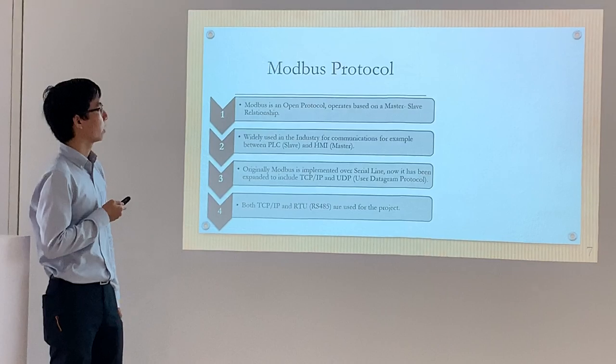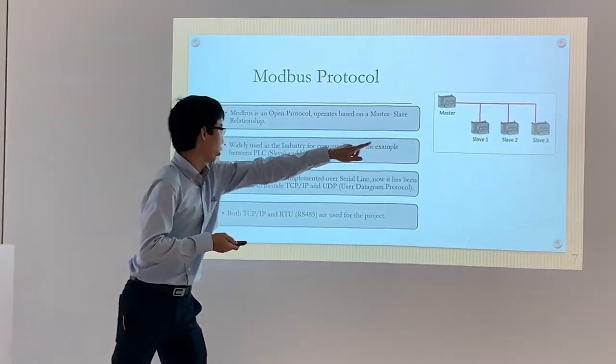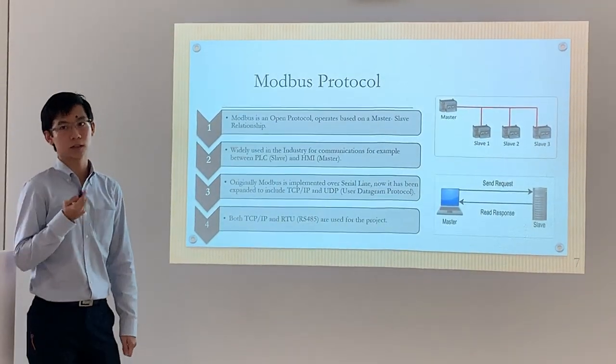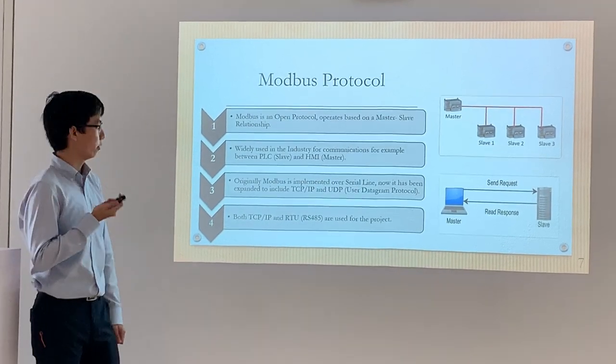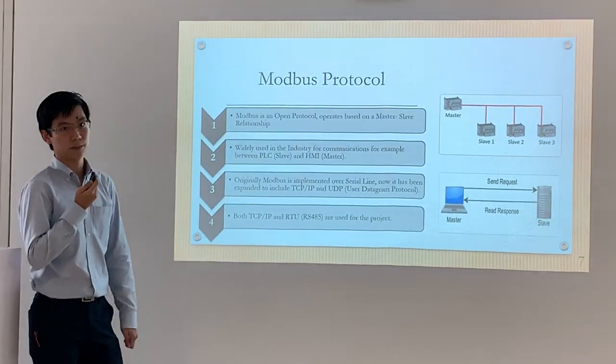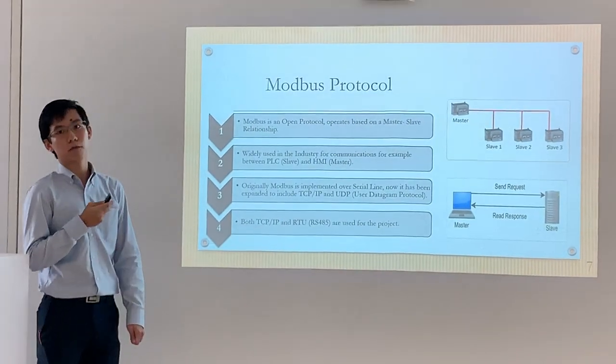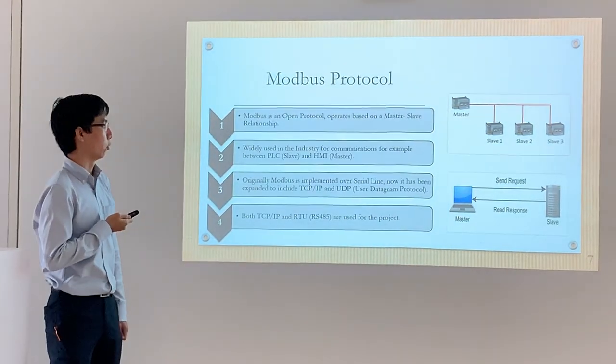The Modbus protocol is an open protocol based on the master-slave relationship and it's widely used in industry. The PLC is the slave and the HMI is the master. Originally Modbus was used for serial communication but now it has been expanded to support TCP/IP and UDP. For our project, we use Modbus TCP/IP and Modbus RTU using RS485.